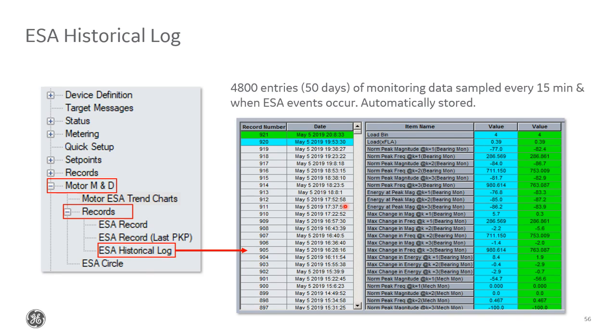Aside from allowing you to see what's going on over time, this log can give you an indication of how widely your readings fluctuate if you were to look through all of these. If your motor has regular fluctuating frequency magnitudes, or if they generally stay pretty consistent, you should be able to see that if you look through all of them. This could help you to tune in the pickup settings to lower values while avoiding false pickups. Normally, we set it kind of conservatively to start, and then you can adjust based on what you're seeing here.